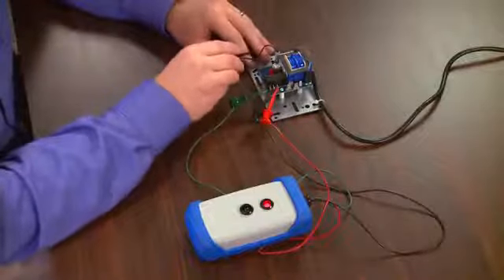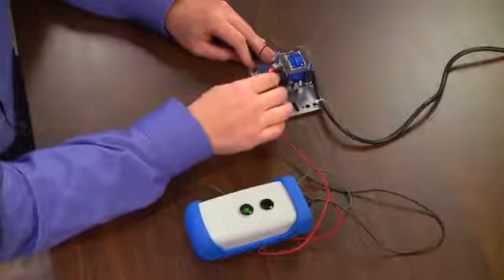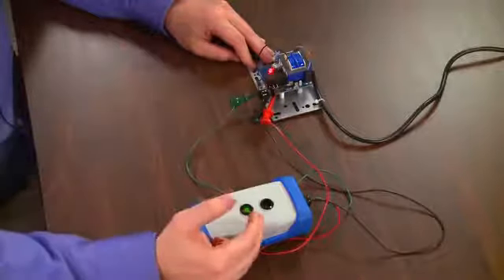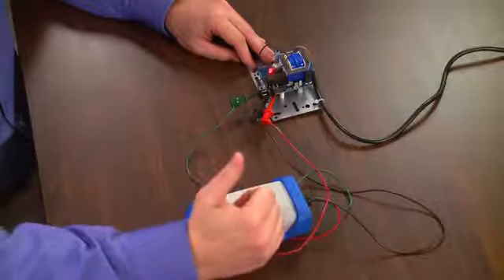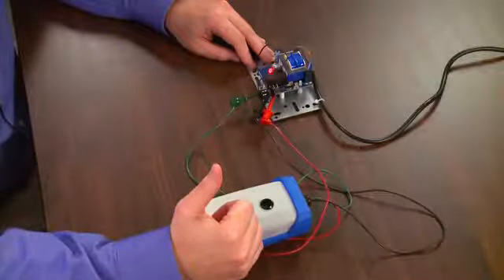Now in a single level service direct mode when water hits the high probe LED comes on relay is energized you notice that the lights have changed state. The normally closed contact becomes open the normally open contact is now closed.